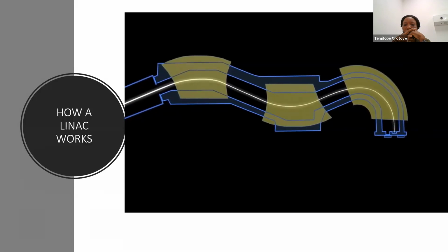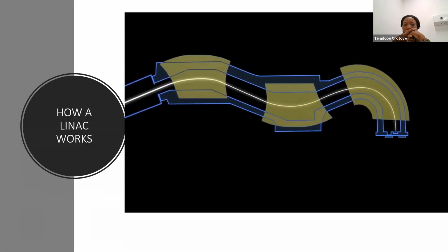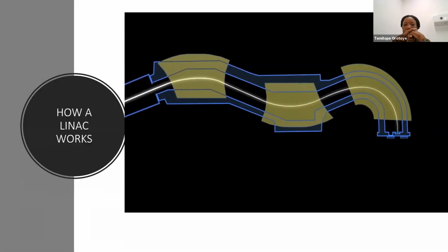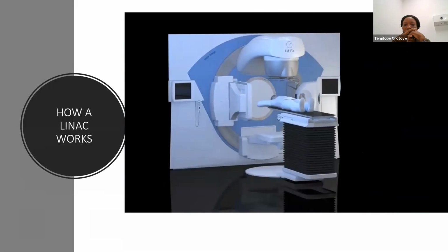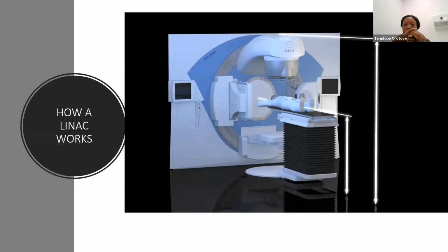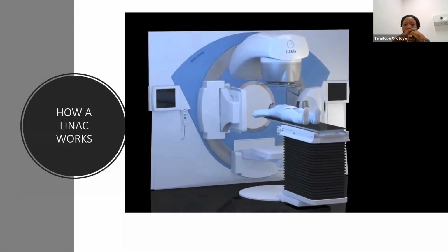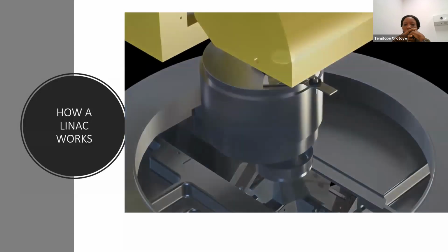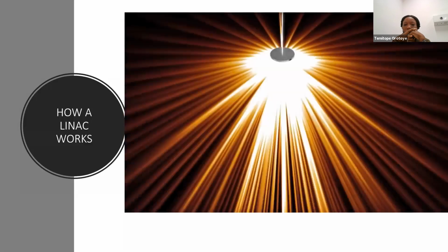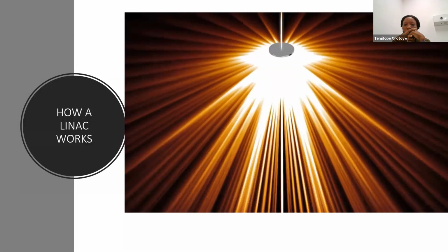The design of the magnets enables them to focus electrons of slightly different energies onto the same point on the target. This is called achromatic behavior. This slalom bending is unique to electrolinear accelerators. It helps to minimize the size of the machine and ensures that its isocenter remains low, which is important for patient setup. The high-energy electrons hit a small tungsten target where the electron energy is converted into photons, or X-rays.